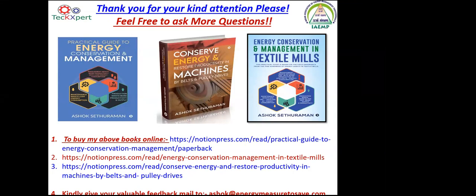Thank you, sir. And this is another question. What is the effect of leading power factor? Leading power factor causes voltage fluctuations, and definitely the system becomes unstable, and there will be problems with all your electronic subsystems, metering, or any of the actuation, PLC or electronic drives. Leading power factor is a curse to the industry, and the industry is in full control to see that it can be avoided. If you go for unity power factor, this leading power factor will definitely come in your APFC. Don't go for unity power factor at all. Try to maintain 0.95 to 0.98. Automatically, it can be avoided by going for a 3cc setting also.